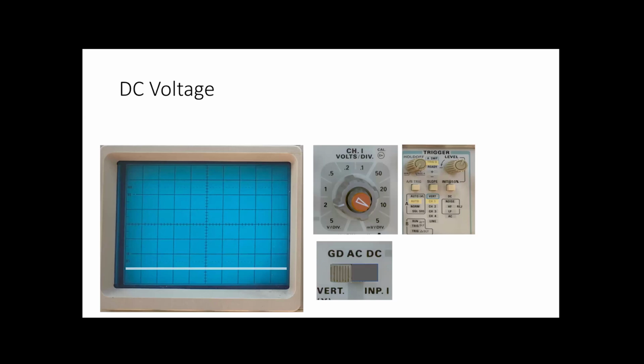Let's see how it's done. Channel 1 I've set to 2 volts per division, and I've grounded it. And my trigger I've set to automatic on channel 1. So now it's triggering and it's drawing a line, and I swizzle that line down to there. That's 0 volts now from here on out. Then I switch my input to DC. I leave it on auto. I connect the scope probe to the circuit and it moves up there. Having moved up there, I measure from there to there, 5.7 divisions at 2 volts per division is 11.4 volts, which is fine.